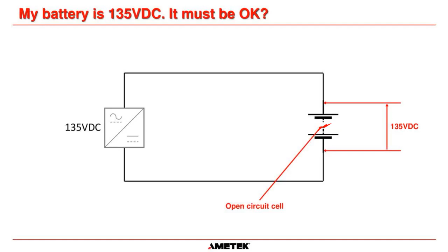This is explained here: let's say you have an open circuit cell in that battery, but the battery is still connected. You will never find that fault if you just measure positive to negative and read 135 volts DC, thinking that means the battery is good. Nonsense. If you turn that charger off, your battery will fail immediately because it has an open circuit.